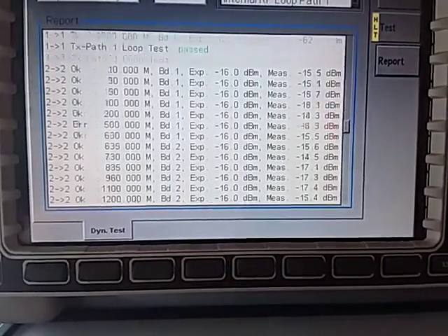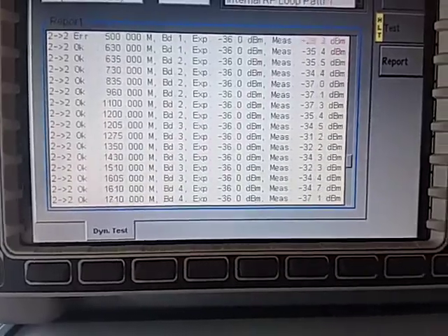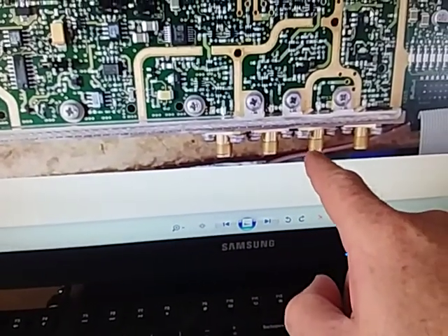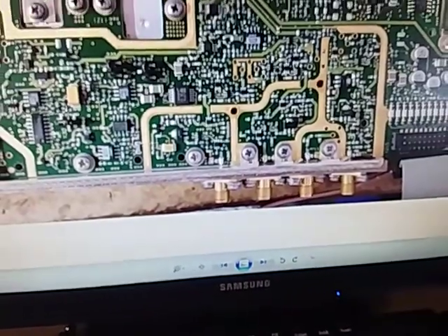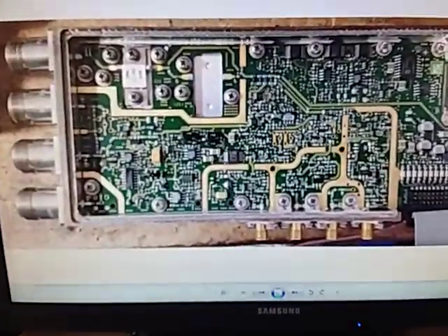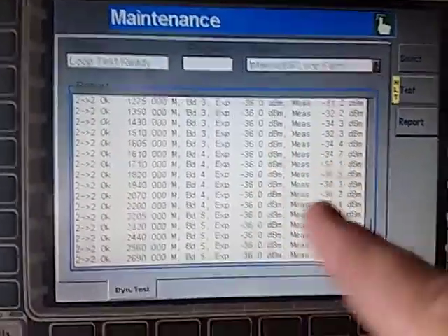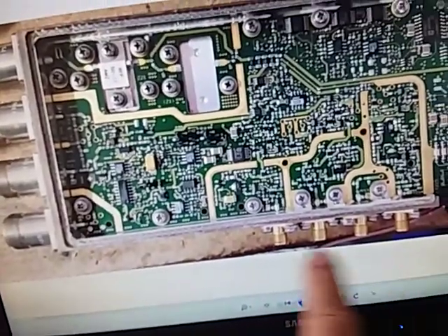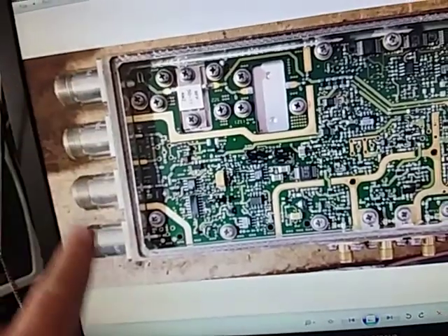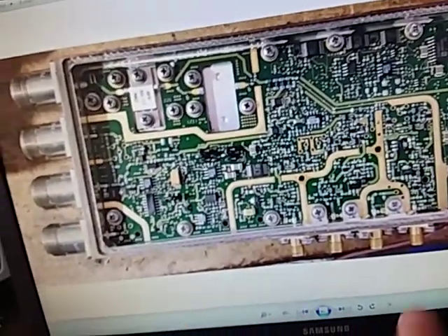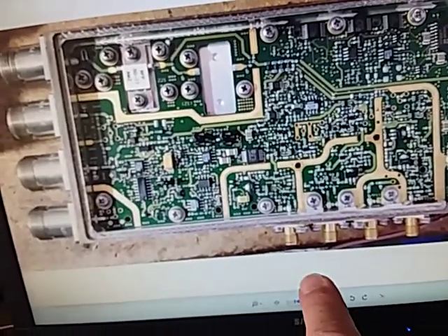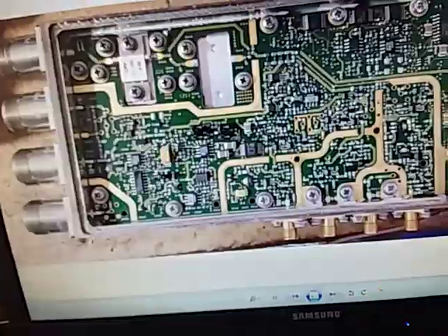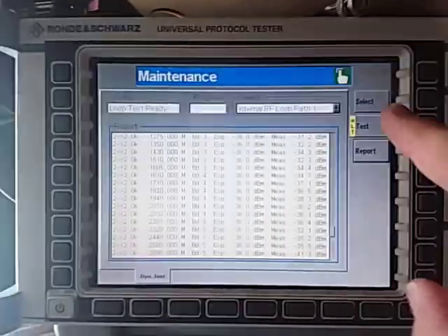That's interesting. That says to me that one of my connectors inside the analyzer, I'm thinking the fault with my analyzer is when I was last in there, I may not have done one of these nuts up properly on these SMA connectors. So it could be as simple as that. Just shows you how important it is to check your work, I guess. You can see the internal loopback test tested this path, these paths down here. They didn't test these, that was the external paths that we did first off. So now I know that the fault in my analyzer is more likely to be around here. I know where to go looking inside the analyzer. So that's how these self-tests can help you out.